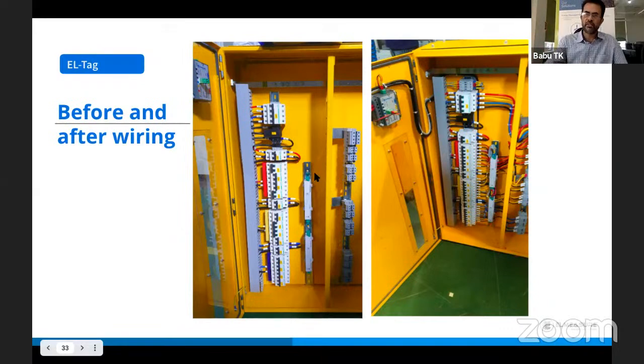They weren't planning to introduce any measurement devices on the distribution side. We pitched in and said, look, you don't need to redesign the whole thing, we can do that. So we went and placed these things just close to this. You see this distance of MCB, about 90 mm, and the gap you have is about 90 mm. This EL-Tag has a dimension of about 25 mm, and the whole wire goes through it, that's what you see on the right side.